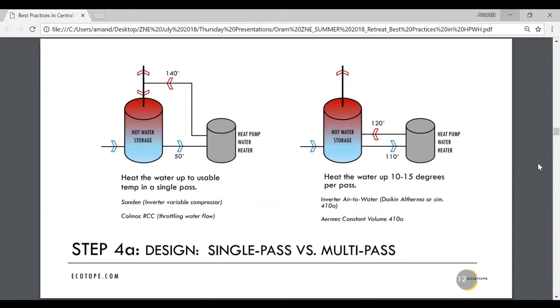Can you talk about pairing with solar thermal and that temperature difference degradation? That's an interesting conversation. On a big central system, as opposed to doing a preheat, I would set it up as stage 1, regulate the flow, take it up to your collectors, slow it down and make it a single pass machine. When that's not available, go to the heat pumps. That's how I would deal with it.